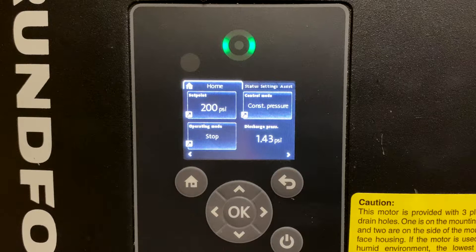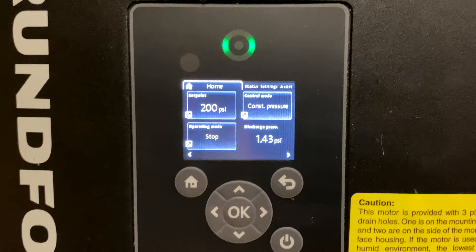Initial startup of your new Grundfos pump is very simple and easy. After all electrical and water connections have been made and three-phase power has been turned on, you will notice the display screen automatically illuminates and will show you the output pressure setpoint. You will see that the pump is pre-configured in the constant pressure control mode and is currently in the stop mode when idle.